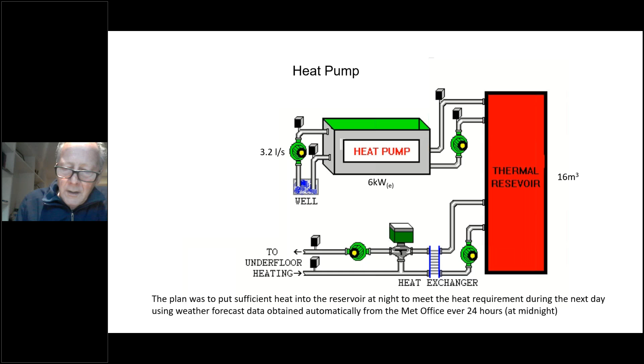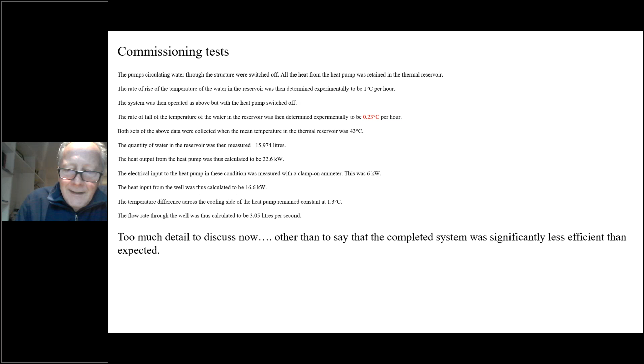The benefit of that reservoir was it was a super device for testing the performance of everything, because we were able to use it as a stable, constant heat load because of the standing losses from the reservoir. And I won't go into the details, but when we tested everything, the building, the heat pump, the borehole itself, the completed system was significantly different to what we expected. There was much greater loss. So we set about trying to correct the faults that we saw in the constructed project.